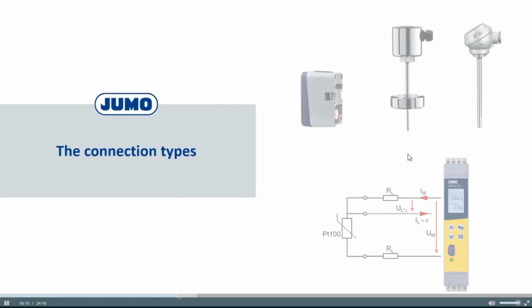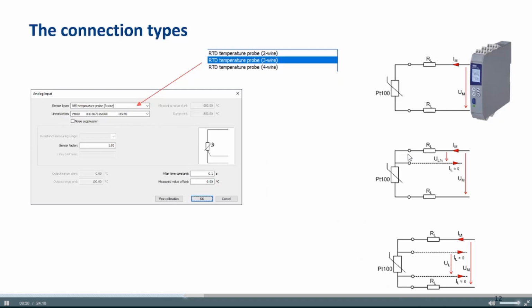Now, I want to give you information about the different connection types. How can you connect an RTD temperature probe to a field device? In general, we have 3 possibilities. We can connect it with 2 wires, 3 wires, and 4 wires. In a few minutes, you will see that with 2 wires, in many cases, you have a drawback. This is standard. And if you want to reach the best accuracy, then you work with 4 wires.